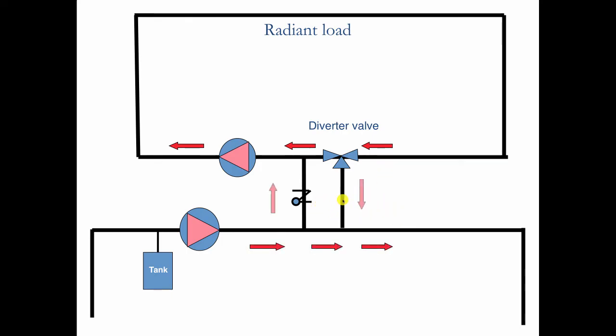But now look, this is the flow. I've reversed this check valve. So now when the diverter valve moves its position, the hot water will come here. And by doing this, when this port closes, I still have access, pressure-wise, to the compression tank, so this will not cavitate.